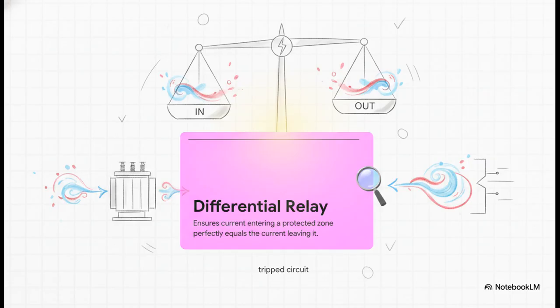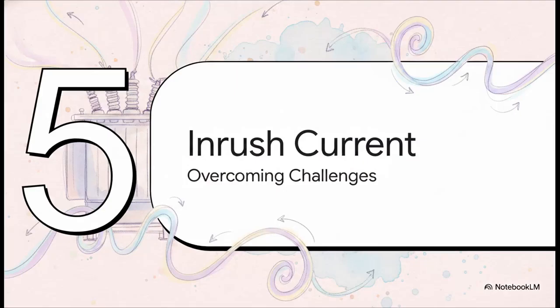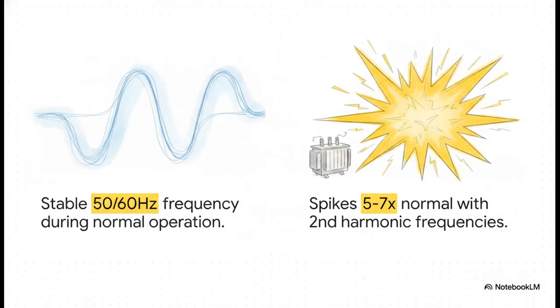It immediately signals an internal fault and trips the circuit to save the equipment. No exceptions. But that strictness leads us straight to Section 5, Overcoming Inrush Current Challenges. Because honestly, that strict accounting creates a massive headache when we're simply trying to turn the transformer on. When you first energize a transformer, it gulps down a massive amount of power. We call this inrush current, and this can spike 5 to 7 times higher than the normal operating current.